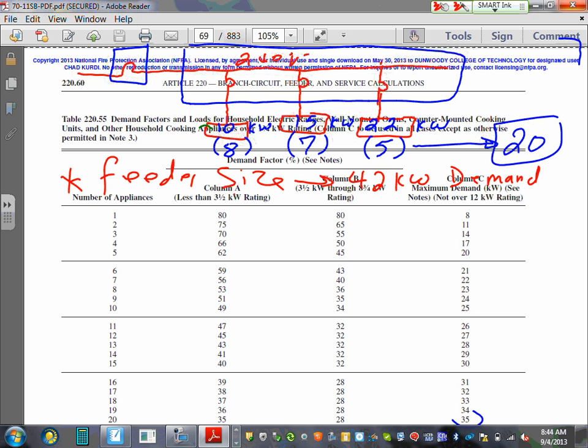A demand means you already chopped it and adjusted it and it's cool. Then you're going to find the amps. I equals 42 kW divided by 240 because the system is 240. Who's my math wizards? 42,000 divided by 240. 175. 175, do I have a second? 175 even? Wow. Weird, jackpot or what? 175 amps. Okay, so that's step number one.